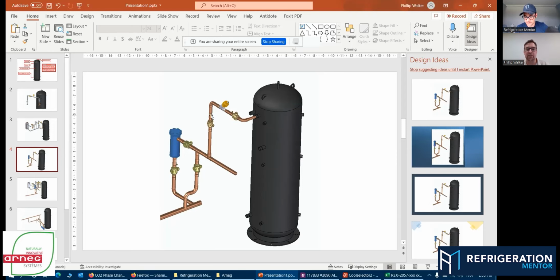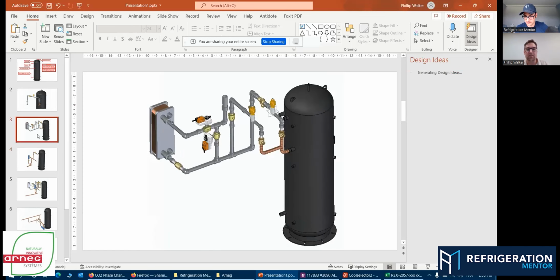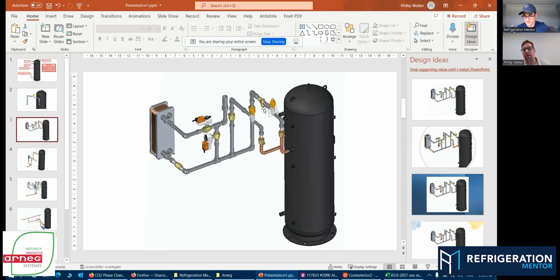Are these valves closing? Is my strainer blocked? So not only closing, is it opening too much? And I think that's something we don't talk about. What's going to happen if this strainer is dirty? What's going to happen to this valve? The system's going to drive it further open. So take a look at your control graphs, and if you've seen that she's been running at 30 to 40%, and suddenly there's a little hiccup in the piping, and now she's driving 60, 70%. That's an unusual occurrence, right? You might want to take a fine look at whether this is blocked.